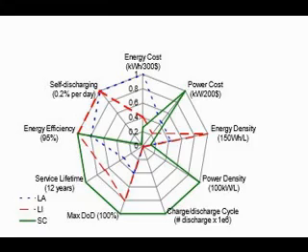The figure above shows the key parameters of each type of UPS battery, which are lead acid, lithium ion, and supercapacitor. Lead acid offers the most inexpensive energy capacity, which is the key reason that lead acid is the most used storage in current UPS. Lithium ion has high energy density, which means it can provide the same capacity in a small form factor.